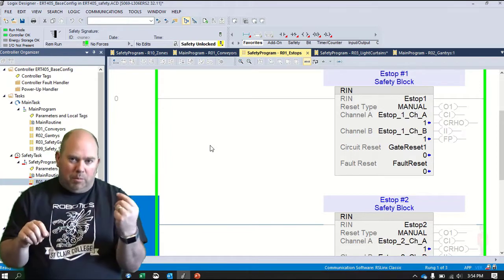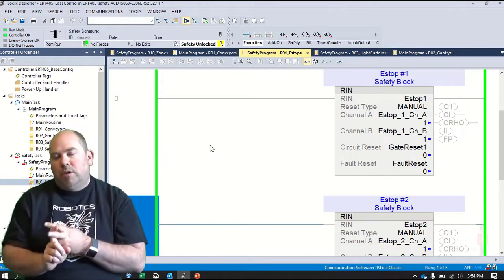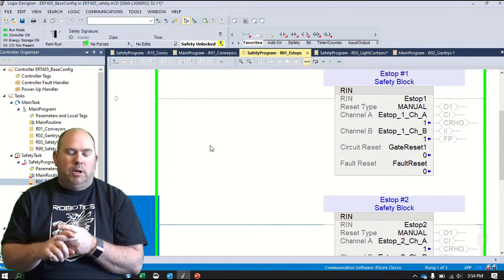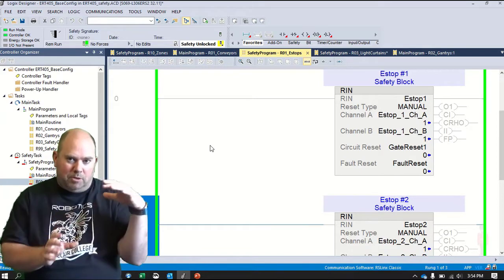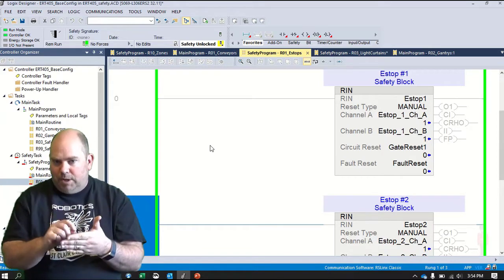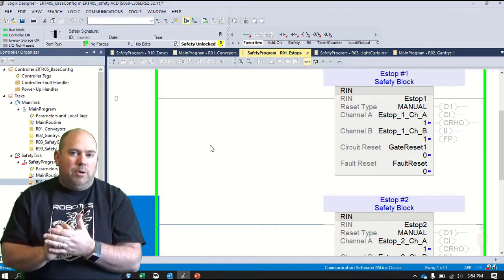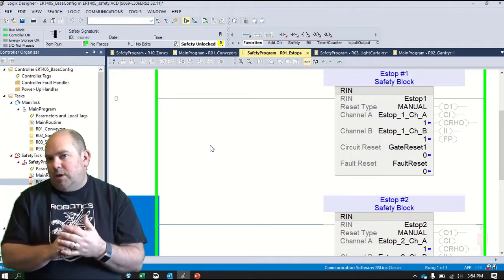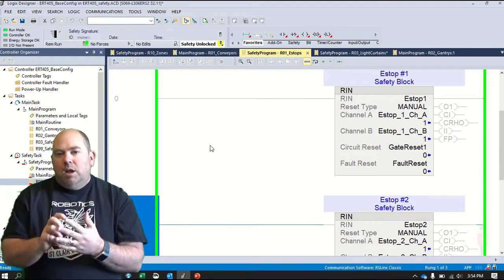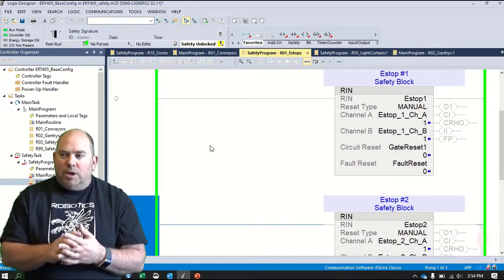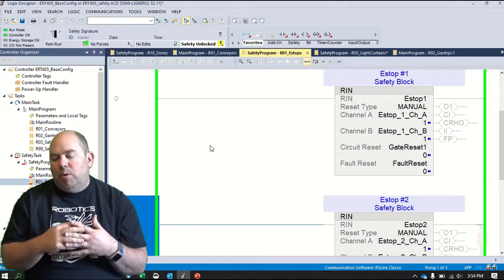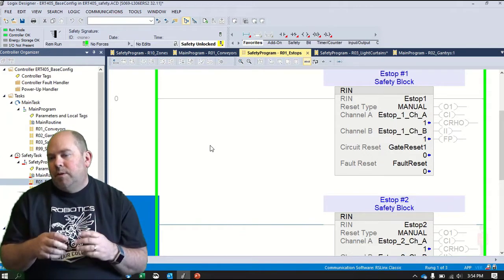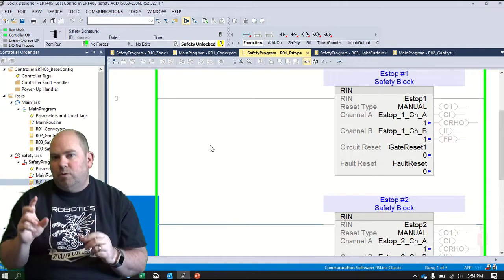Do the same testing. This is all part of the validation process. So we're going to have to do that for every single device. We're probably going to create a big checklist, go through, validate, validate, validate. Check all that. Check all your inputs. Check they shut down the zones like they should. Check that everything faults like it should. Check that all your outputs function properly. And once all that validation is complete, your safety system is now good.